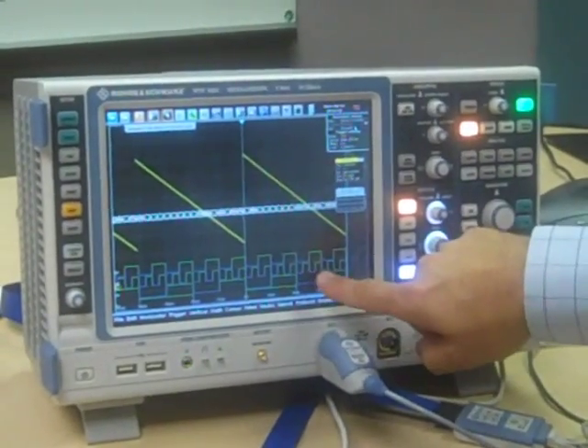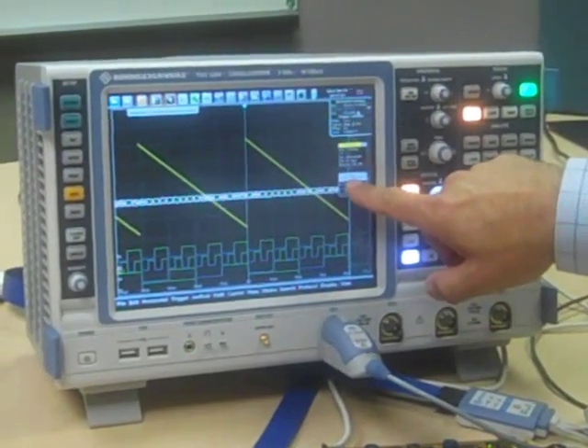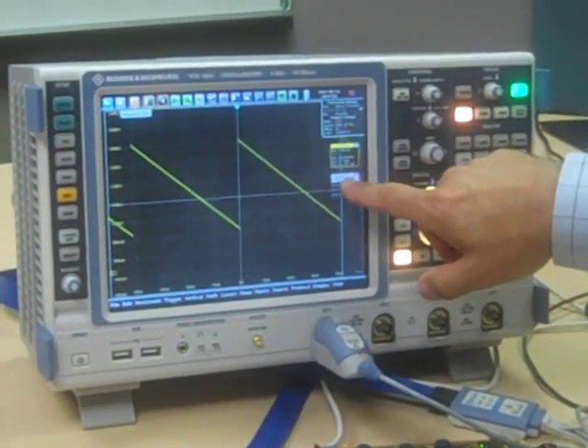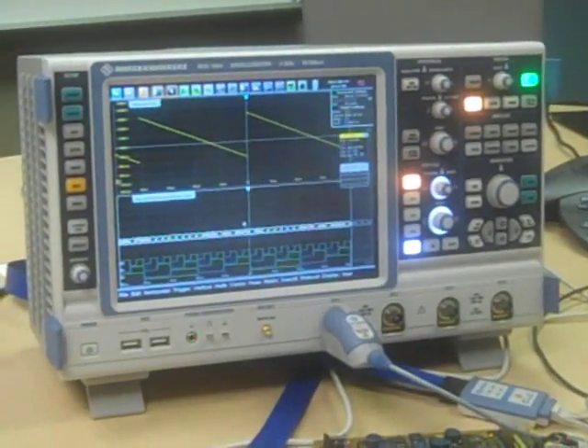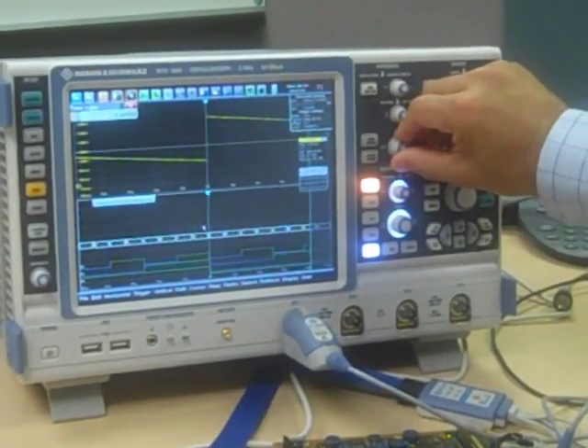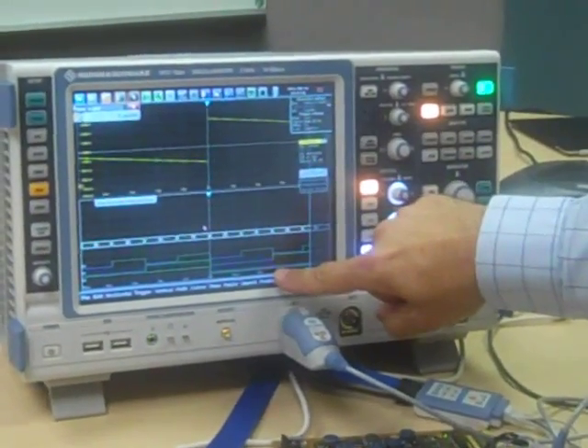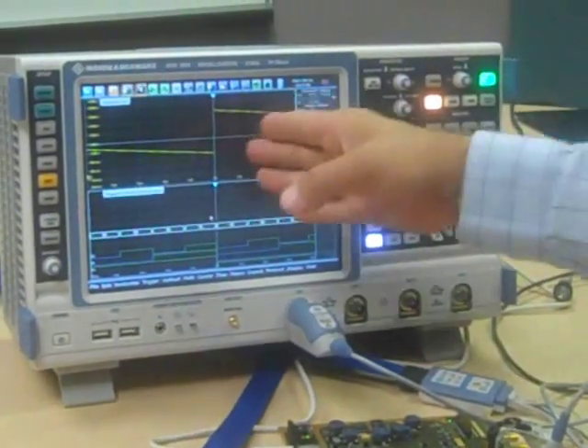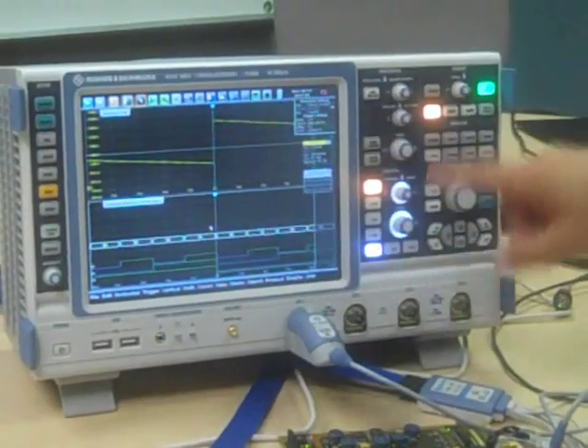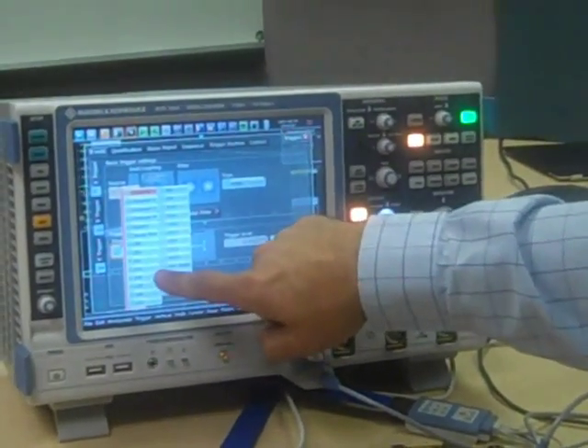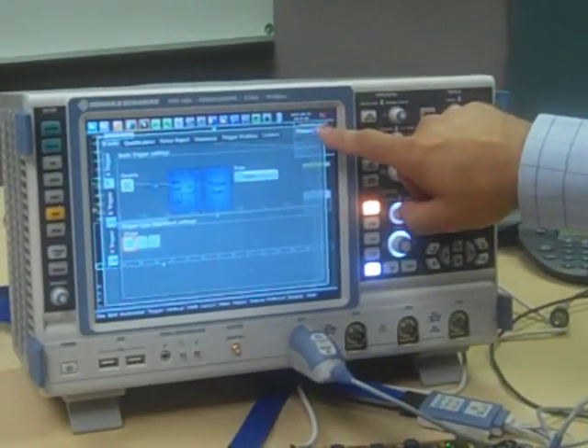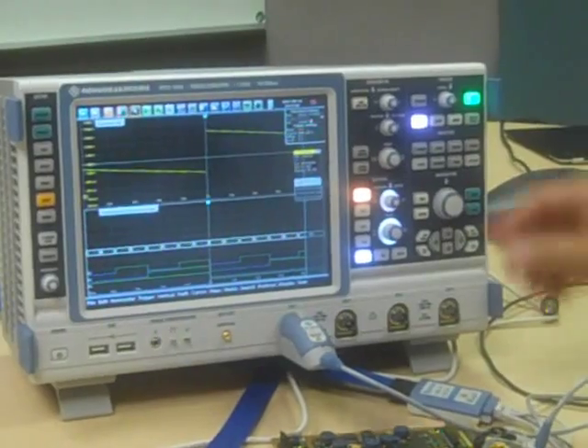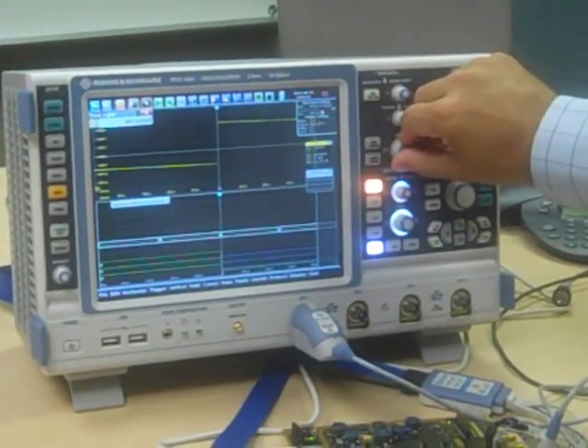Now we're looking at the logic channels mixed in with the analog channel. With my smart grid, I can minimize the logic display and position it anywhere I like, either below or above. We're looking at the bus form diagram above here and the individual bits below. You can see the counts as we're doing the different bits. Right now we're triggering on the edge of that ramp, but we can change our trigger input to trigger off any one of the digital channels. Let's trigger off channel D3, which is our most significant bit of the counter.